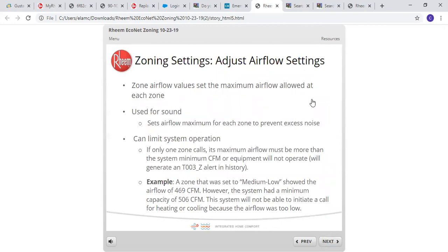So if you want to really fine tune the system, zone airflow values are set at the maximum airflow allowed at each zone. Some of the fine tunings are used for sound, setting the airflow maximum for each zone to prevent excess noise, but this can limit system operation. If only one zone calls, its maximum airflow must be more than the system minimum CFM or the equipment will not operate. If you run into that situation, you'll generate a T003Z alert history. An example: if a zone was set to medium low, which showed the airflow system at 469 CFM, however, the system had a minimum capacity of 506 CFM, the system will not be able to initiate a call for heat or cooling because the airflow is too low. And in return, you will get a T003Z alert.